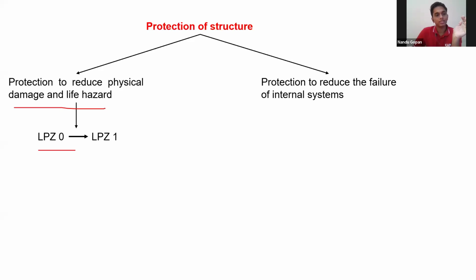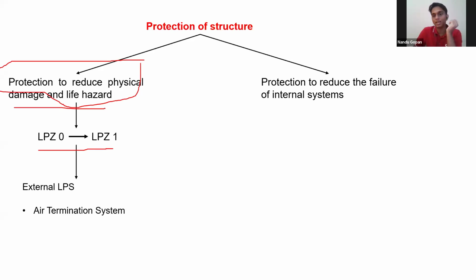...that applies from LPZ 0 to LPZ 1. This is where protection against physical damage applies, LPZ 0 to LPZ 1, and it is called external LPS. External LPS consists of the air termination system, the down conductor, and the earth termination system.